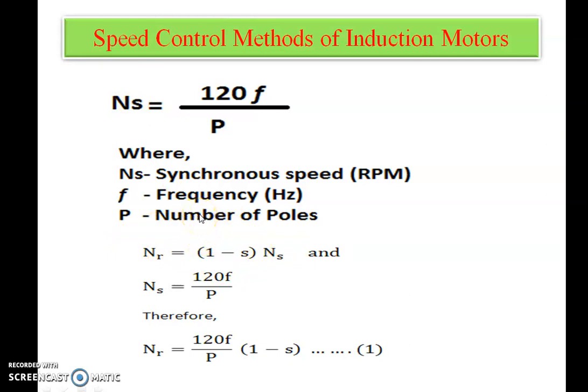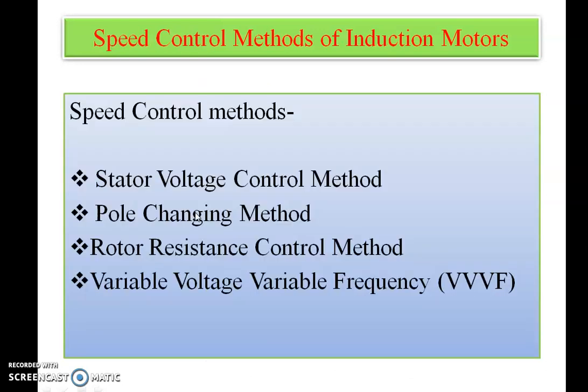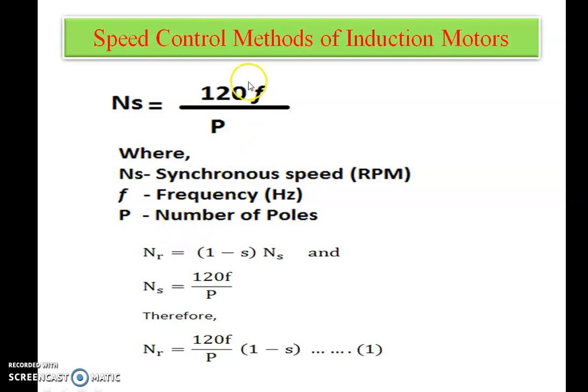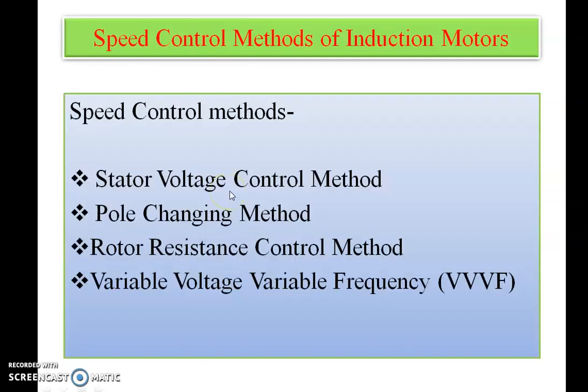So we will see about how the speed control mechanism is applied for induction motors. This is the basic formula used to control the speed of induction motor - we are going to control the NS, and obviously if we control NS it will change the actual speed NR. These are the methods used for speed control: first, stator voltage control method; second, pole changing method; third, rotor resistance control method; and last, variable voltage variable frequency, that is VVVF.